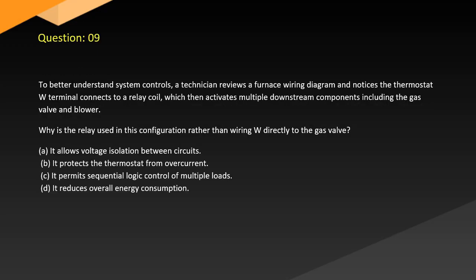Question 9. To better understand system controls, a technician reviews a furnace wiring diagram and notices the thermostat W terminal connects to a relay coil, which then activates multiple downstream components including the gas valve and blower. Why is the relay used in this configuration rather than wiring W directly to the gas valve? A. It allows voltage isolation between circuits. B. It protects the thermostat from overcurrent. C. It permits sequential logic control of multiple loads. D. It reduces overall energy consumption.